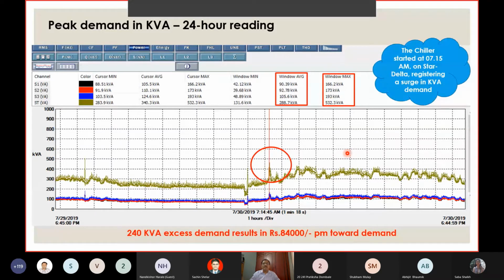What is the impact of this? They are paying for 532 kVA. I think the sanctioned demand is 600. They are paying for 532 kVA, which they need not have paid if they had a device that would prevent a sudden jump in the kVA. So we proposed a VFD. Even a soft starter will not help, because star-delta starting and soft starting are both identical. You cannot limit the starting current to below 4 times. Whereas a VFD can help you start with even 100% nameplate ampere, and the demand can be substantially reduced.